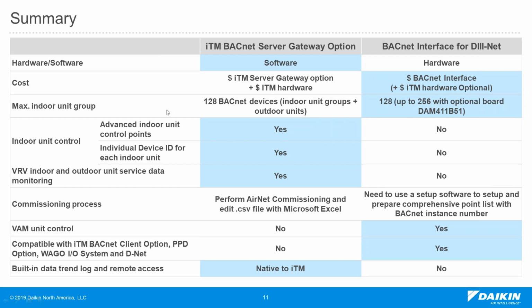For the control capability, the ITM server gateway can control up to 128 BACnet devices. That number includes both the indoor unit groups and the outdoor units. But the hardware gateway can control up to 256 indoor unit groups if you use the additional option board. So I would say the hardware gateway has more advantage when it comes to capacity.